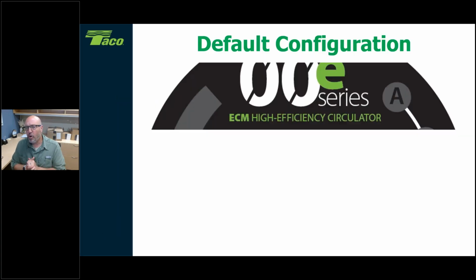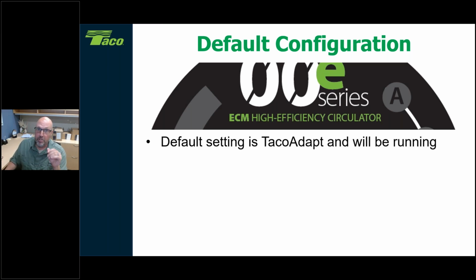All right, so just a little bit of review from last week. Let's jump in. So you turn this thing on. You power it up for the first time, and we're going to talk about how we hook up our power to this thing too. It is going to be in the default mode of TacoAdapt, and it's going to be running. So you put power to this circulator, it's going to start running. Your motor's going to start spinning, so make sure at that point you are prepared to have water in this system as soon as you put power to this thing. If not, you need to make sure you read the instructions a little bit further in order to make sure you power this thing down.